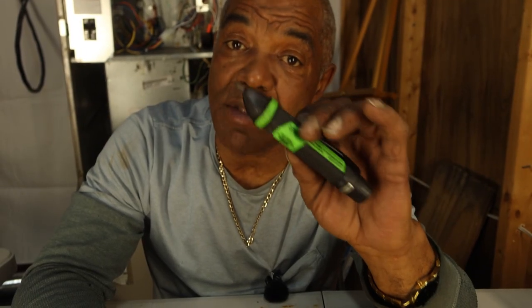It's a voltage tester. Just turn it on, touch the wire, and if there's power in that wire, the light will change from green to red, and it'll begin to beep. It'll do that on the line voltage as well as the low voltage. Awesome time saver in our troubleshooting methods. Let's move to the next.